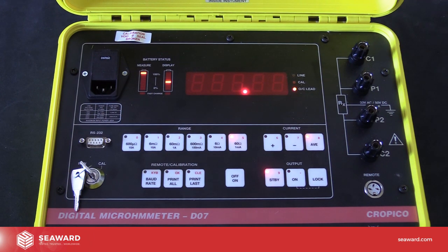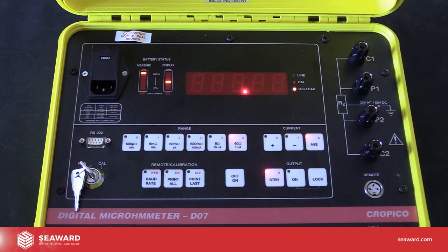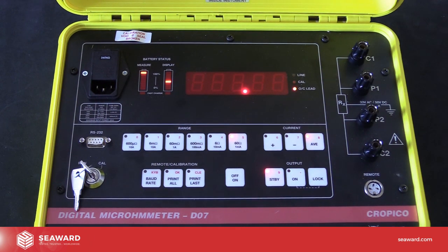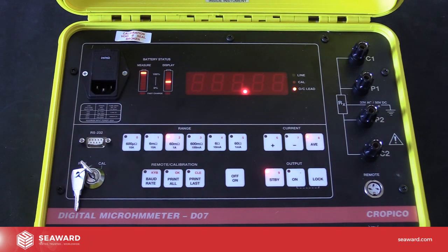The D07 has 6 measuring ranges from 600 micro ohms with a 100 nano ohm resolution up to a 60 ohm range. With that will be the test currents, and you'll notice that they range from 1 milliamp at the highest range to 10 amp measuring current down at the lowest range, and it is at 10 amps where we can get up to 1 hour's worth of continuous measurements. You'll notice as selected the range will glow with the red LED, highlighting easily to the user exactly what range has been selected.